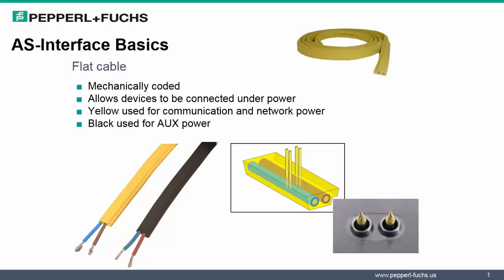As far as AS Interface infrastructure, the yellow AS Interface flat cable has an important role. This cable permits simple and fast installations. The trapezoidal profile prevents lead reversal when connecting modules. Contact is made with two spade contacts. These penetrate the cable when the slave upper part is clamped down on the lower part. The protective shell of AS Interface cable consists of self-repairing insulation material, which closes the contact point upon its release.